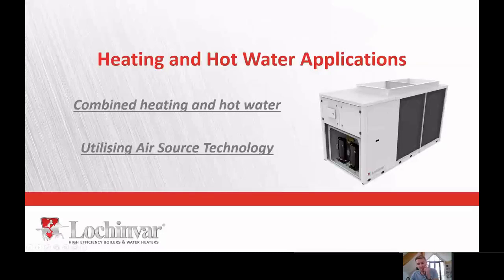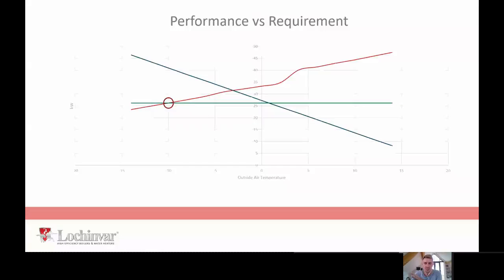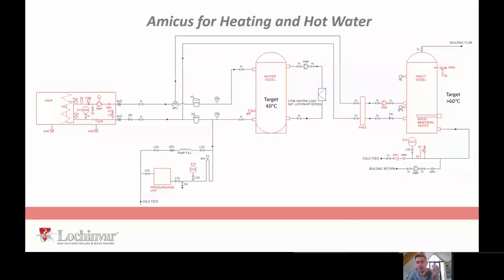Okay, so that was a hot water application. And now, very quickly, just to express the versatility of an air source heat pump and what they're capable of. I'm not going to labour this chart because it is even more of the same in terms of graphs, but from an application point of view, this is how you would address a heating and hot water challenge from an electric air source heat pump. So obviously different manufacturers' heat pumps will vary. I'm speaking for Lochinvar's heat pump here, I suppose, because that's the one I understand the controls on best.